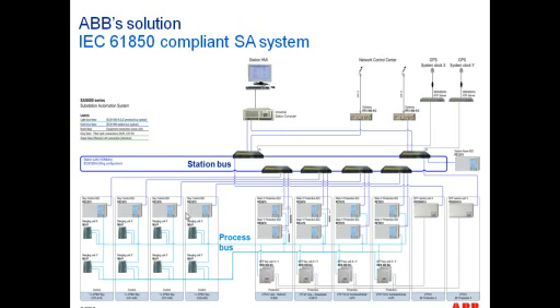These 4 protection relays were the ones providing bay control capability for each one of the breakers, and then these devices right here were providing, some were providing differential protection for the 2 transformers, some were providing differential protection for the 2 outgoing lines out of that substation, and then we had a bus differential scheme based on a distributed REB 500 scheme.